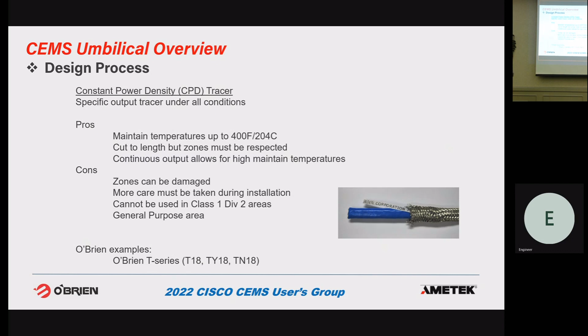So you get to the end of the tracer. You have 2 bus wires, you have dielectric in between, and you have a heater element wire that runs around the outside. You push the ground braid back out of the way, get to the 2 bus wires and the heater element wire, use a multimeter, and measure the resistance from the heater element wire to one of the bus wires, record that value, then to the other bus wire, record that value.